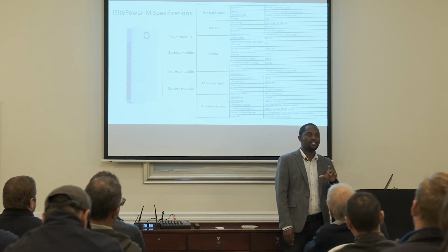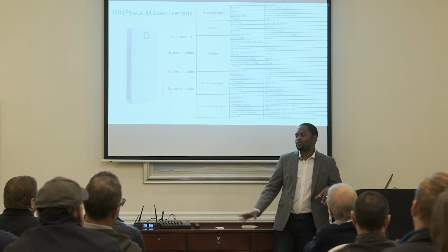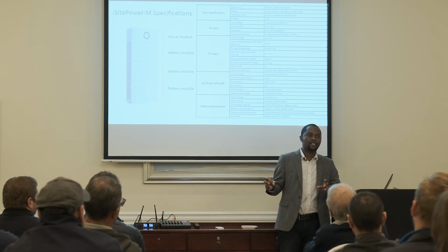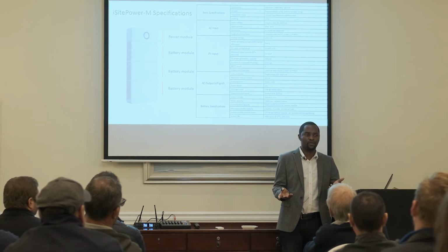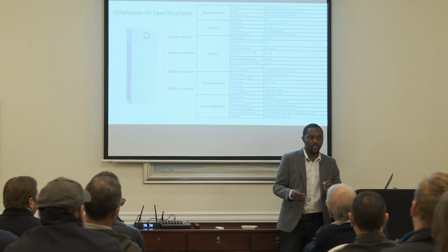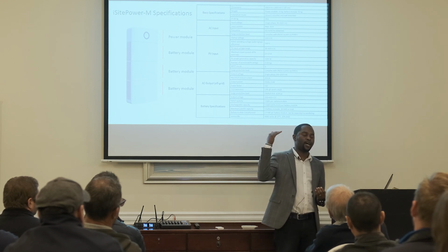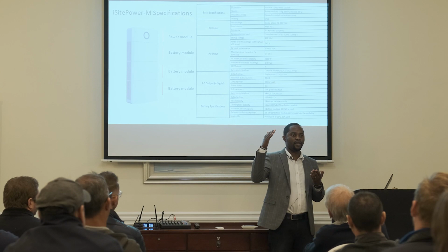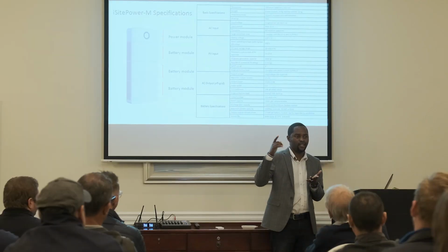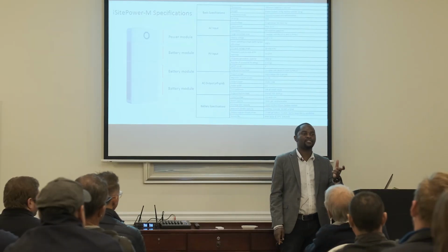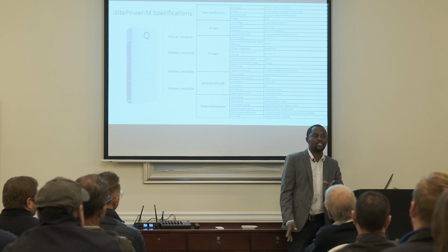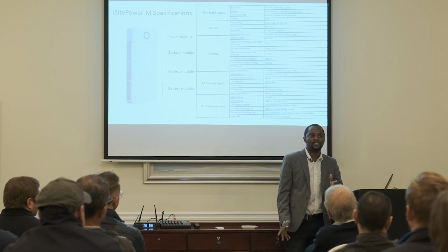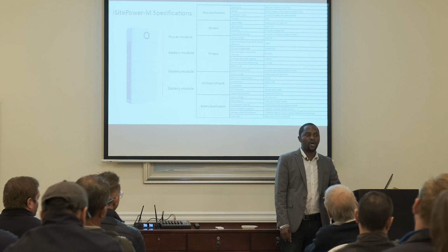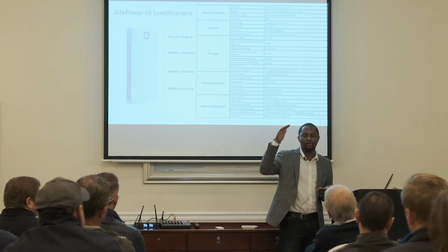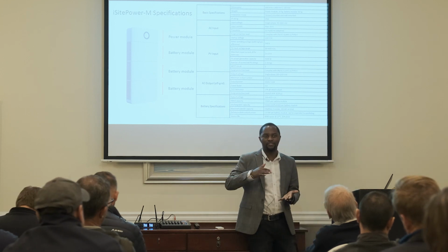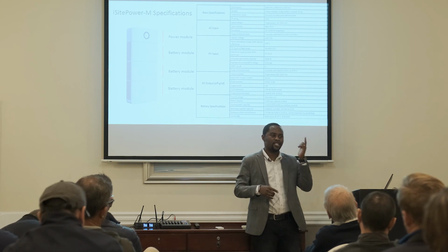Then the Huawei has got a system, unlike all the other systems, that actually gives you what is called half cycles, unlike all the other battery systems. This means if you drain it, let's say from 100 down to 65, and then you charge again, that is considered a half cycle, which means you can have 6,000 times 2, 12,000 half cycles on this unit. Unlike the other batteries, the moment you drain from 100 to 85 or to 70, it's considered a cycle.